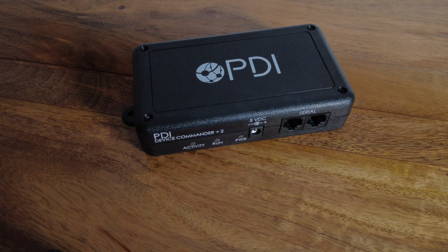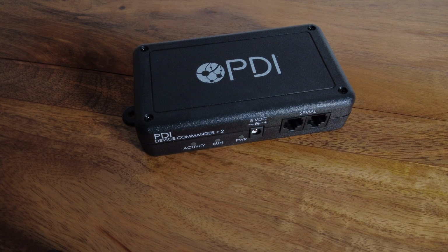For Incon, the serial connection is built in, and then when you're dealing with the newer tank monitors, which are network-based, you simply need to run a network cable from the tank monitor to a switch, plug the PDI Device Commander into the same switch, and set the IP address in the tank monitor to something that's going to be in line with the PDI device. And the PDI help desk will help walk you through that. Very simple setup. Very effective, very good at what it does. It's number 1 on my list.